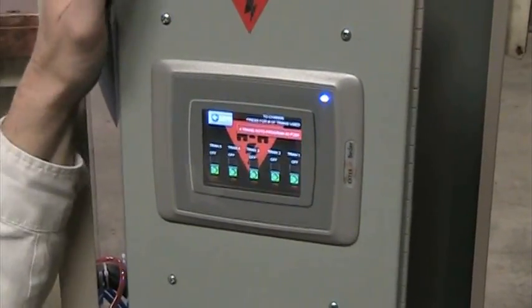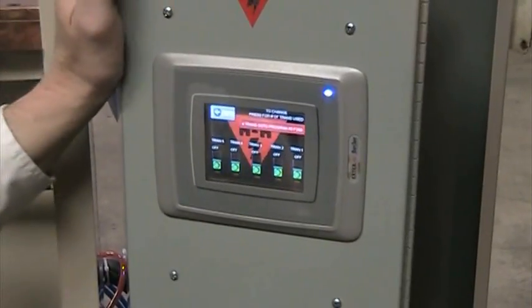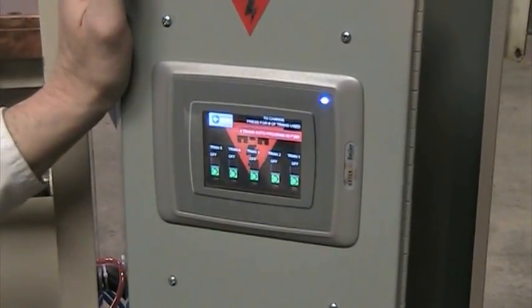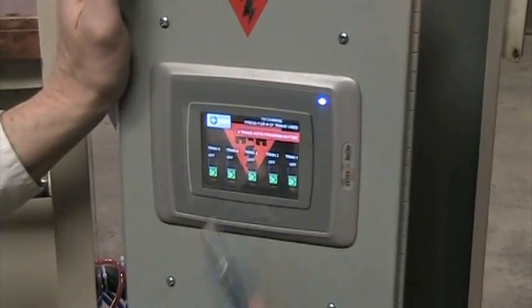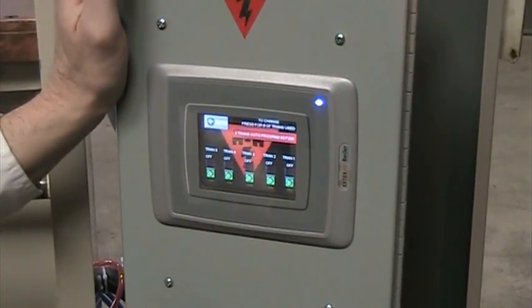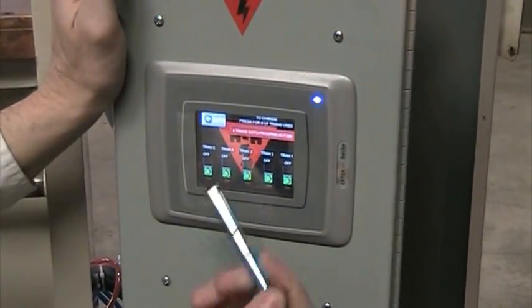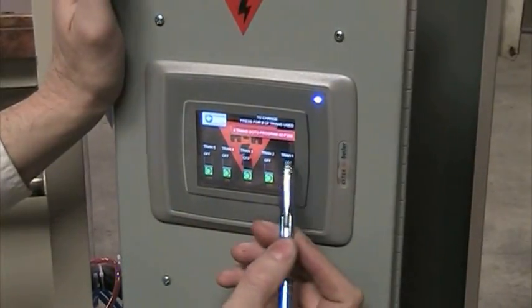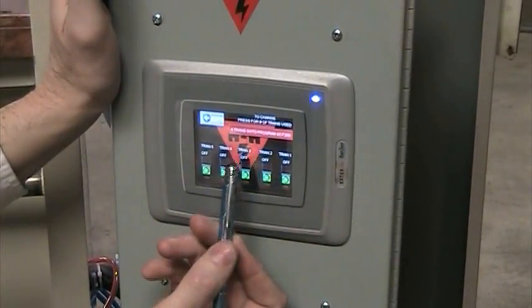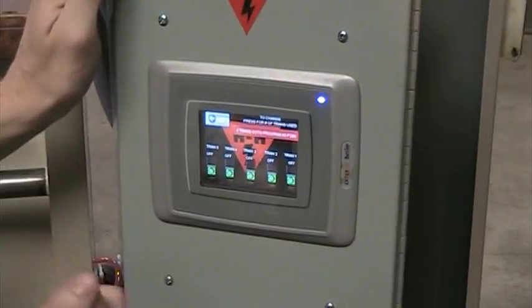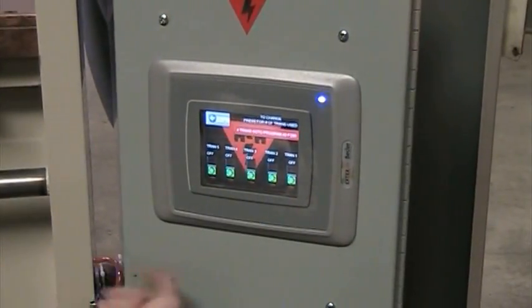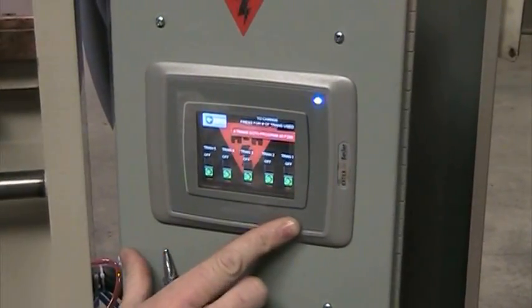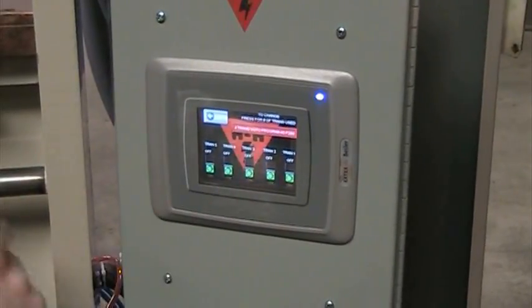Next we'll go to the very top, which is transformer selection. Press it once. We'll go to this section. You can also use any other device. As far as the tip of a pen, I would recommend that you don't use the actual point of a ballpoint pen, but the back end works well. Coming across here you have transformer 1, 2, 3, 4, and 5. And that's spatially oriented the same on the machine. Transformer 1 is the first one on the right hand side, 2 is the next bank, 3, 4, and 5.